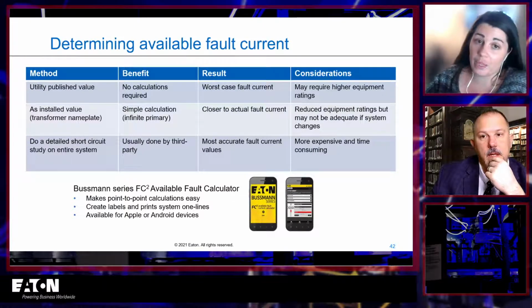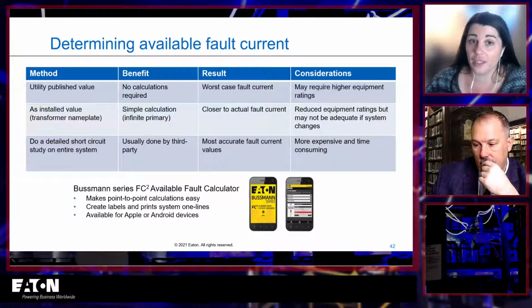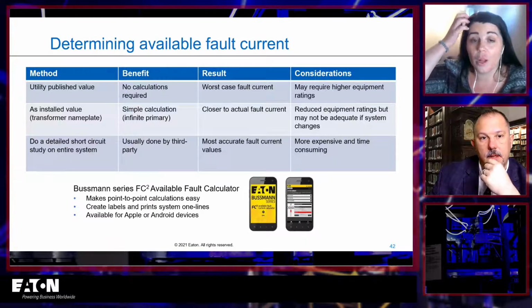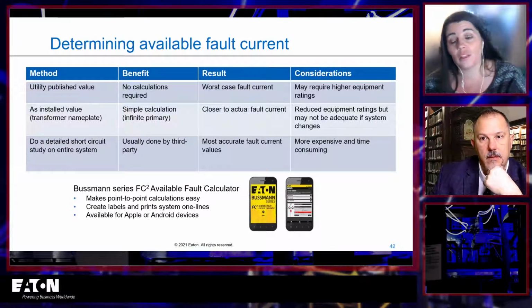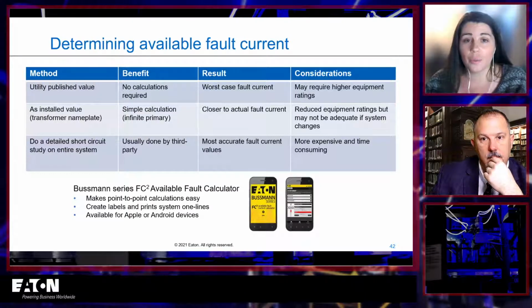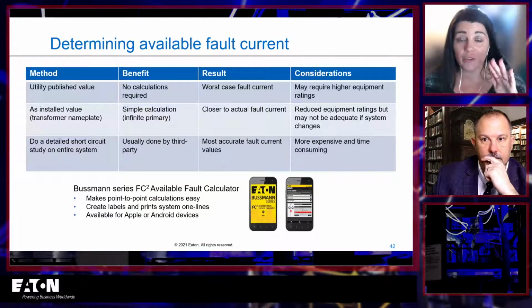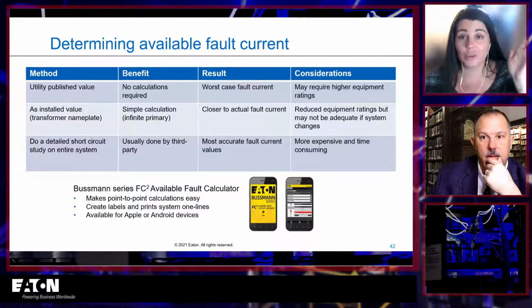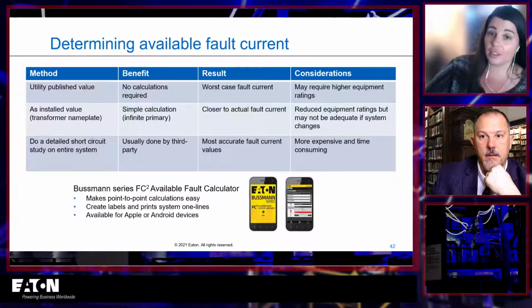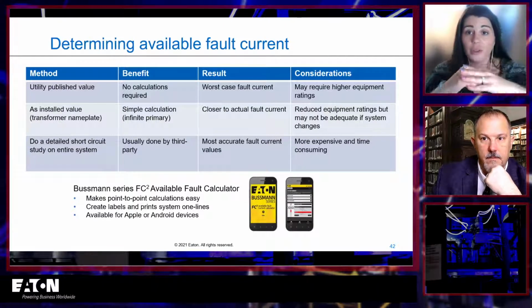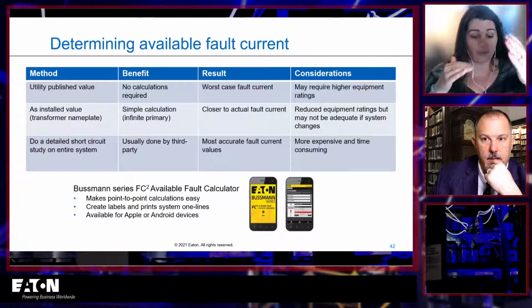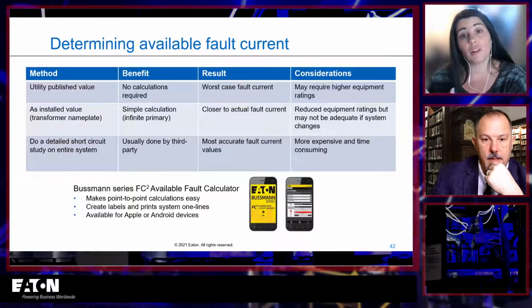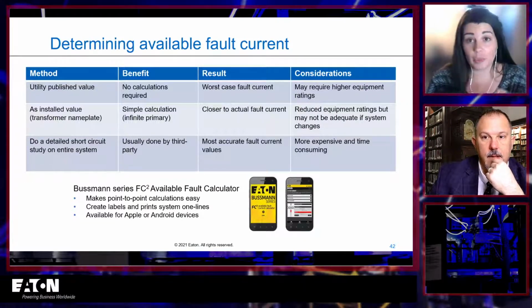This is where the Bussmann FC Squared app comes into play. This is a really, really cool app. You can use it as an online tool, but you can find it in the Google Play Store and the Apple App Store. Download it and just plug in a little bit of information about your system, single phase or 3-phase, and information about the transformer. If you know the available fault current from the utility, you can start with that value and then say, I have this much conductor run. What's the available fault current at the end of the conductor? It'll spit that out for you.